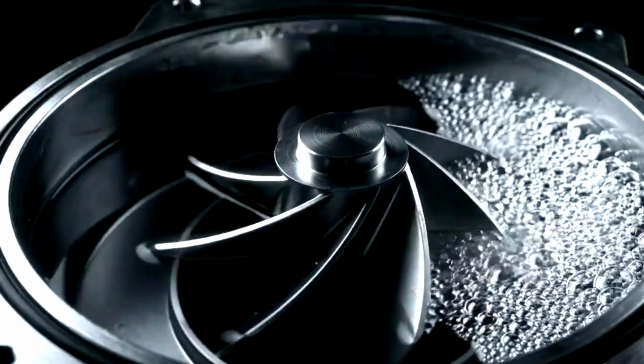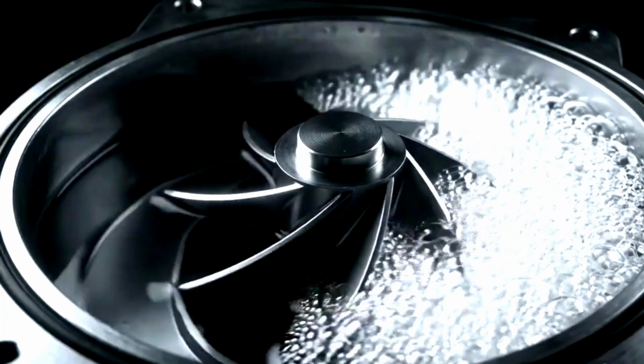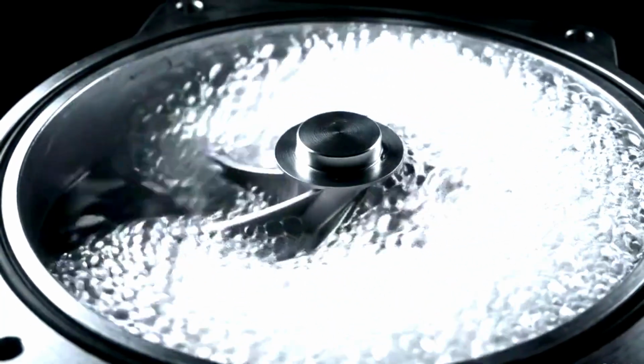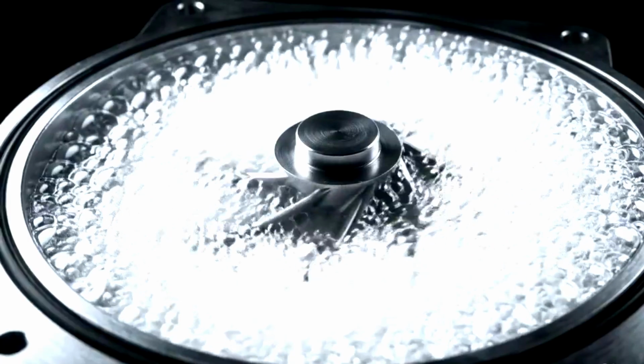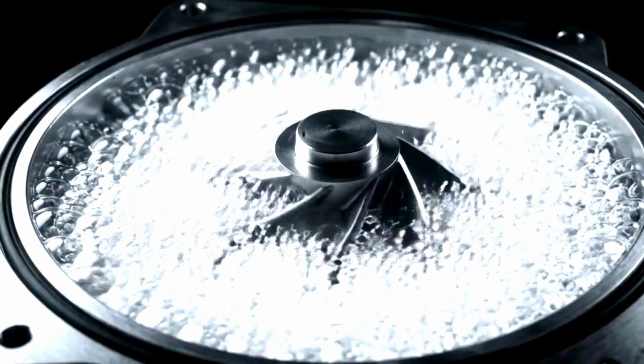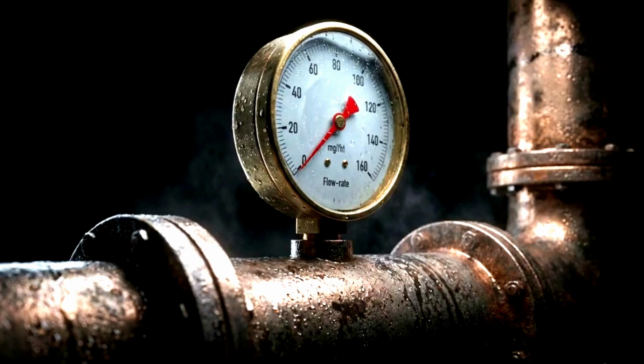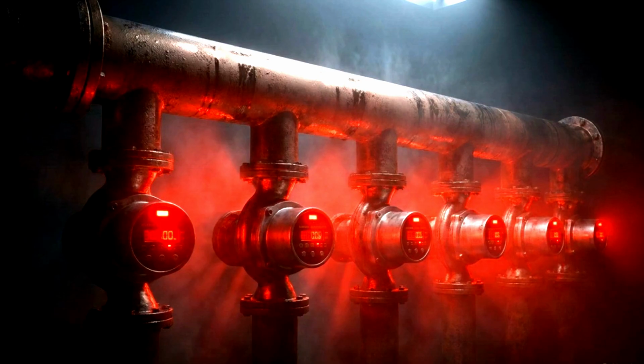This triggered cavitation. The fluid began micro-boiling inside the pumps, turning the liquid into a froth of gas bubbles that the blades couldn't move. The mechanical impact was immediate. Coolant flow dropped by 90% in just 12 seconds. The liquid cooling system was strangled by its own physics. The shared manifold meant that when the pressure dropped, every redundant unit failed simultaneously.